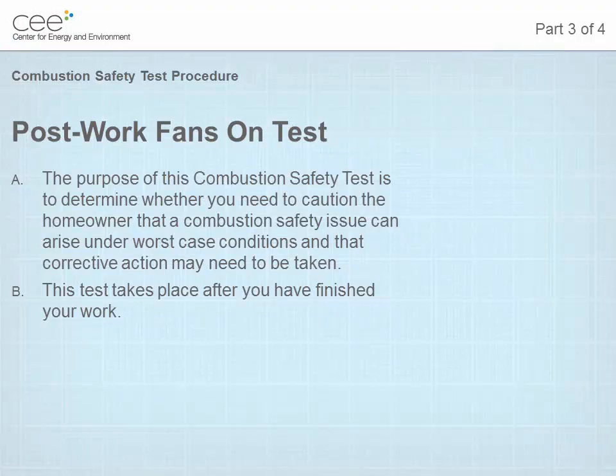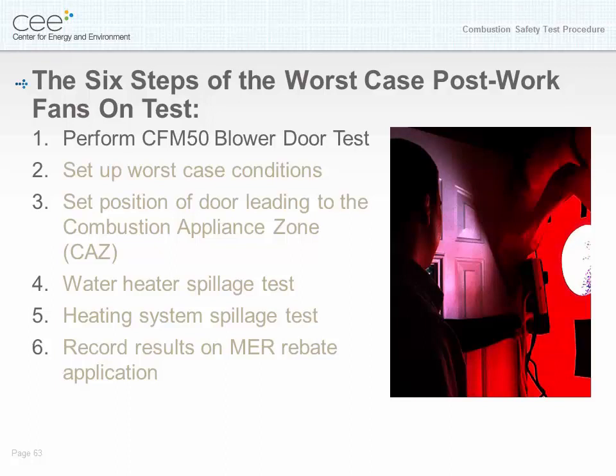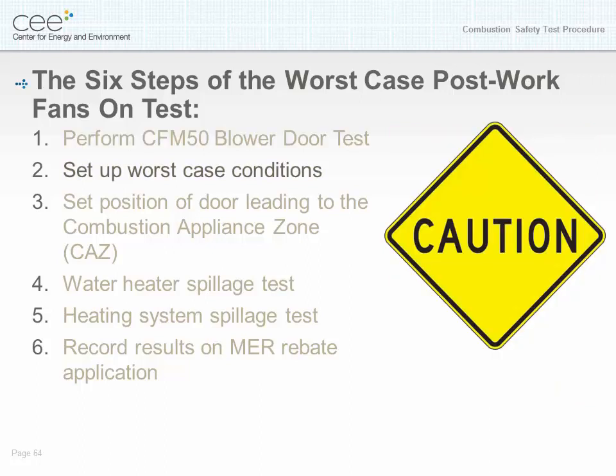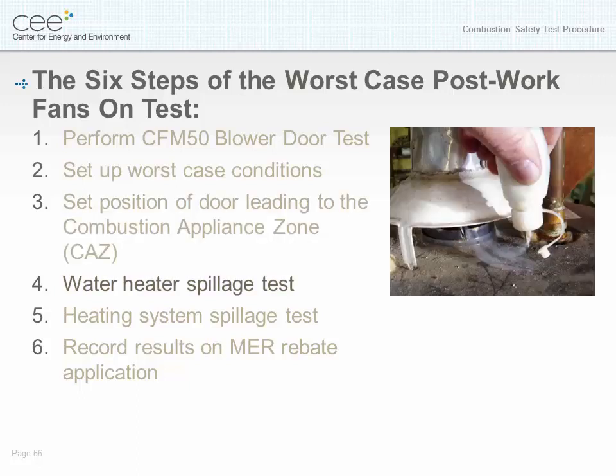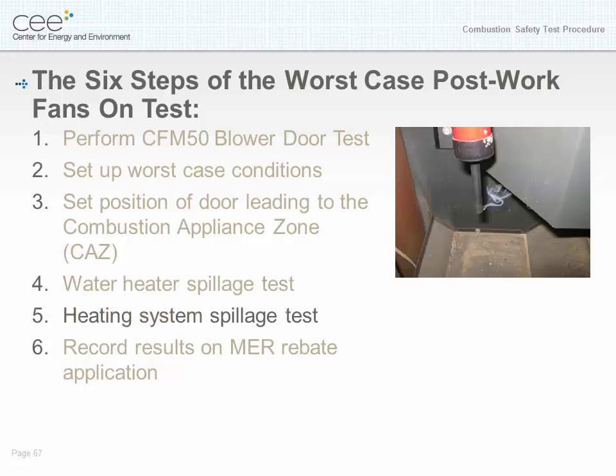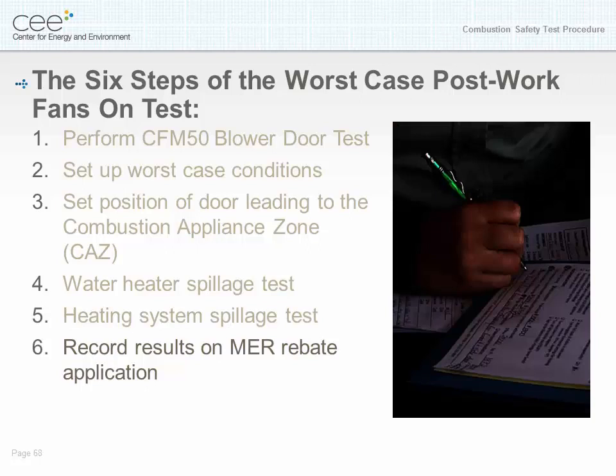Post-work fans on test. The purpose of this combustion safety test is to determine whether you need to caution the homeowner that a combustion safety issue can arise under worst case conditions and that corrective action may need to be taken. This test takes place after you have finished your work. The six steps of the worst case post-work fans on test: number one, perform the CFM 50 blower door test; number two, set up worst case conditions; number three, set position of door leading to the combustion appliance zone; number four, the water heater spillage test; number five, the heating system spillage test; number six, record the results on the MER rebate application.